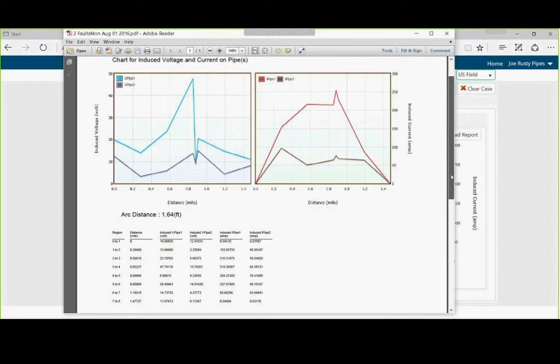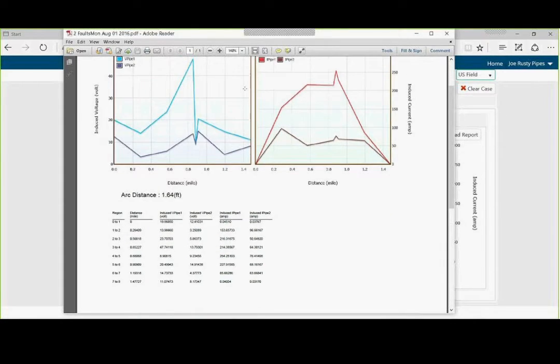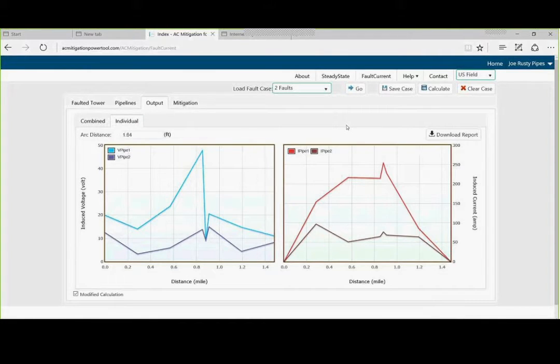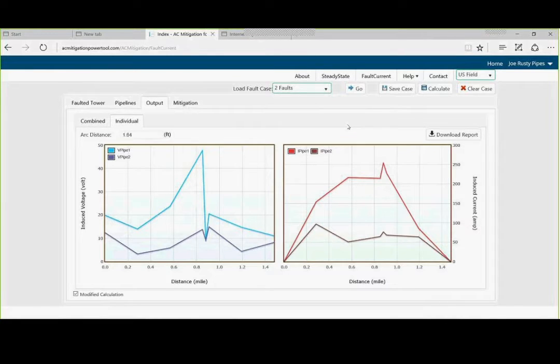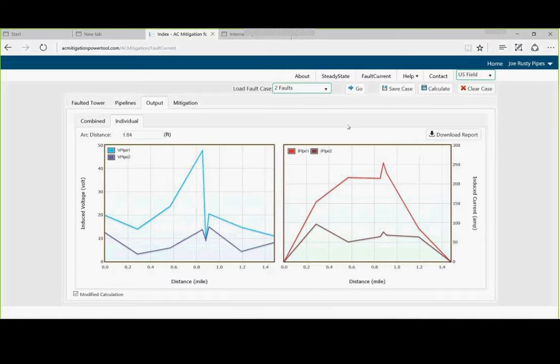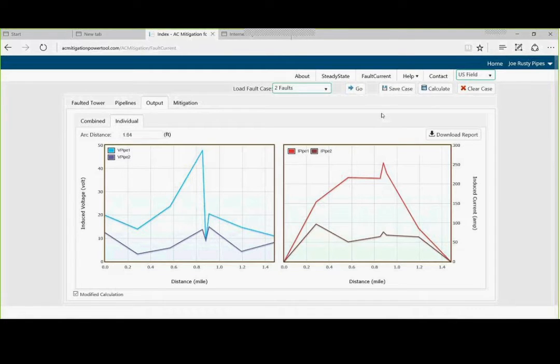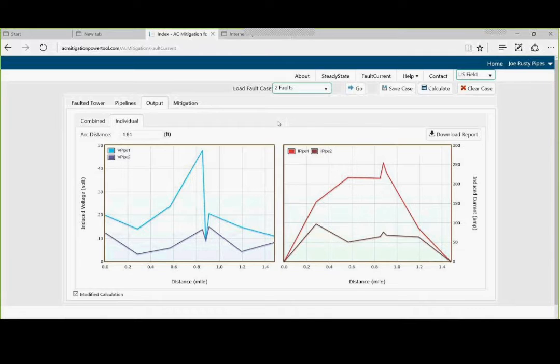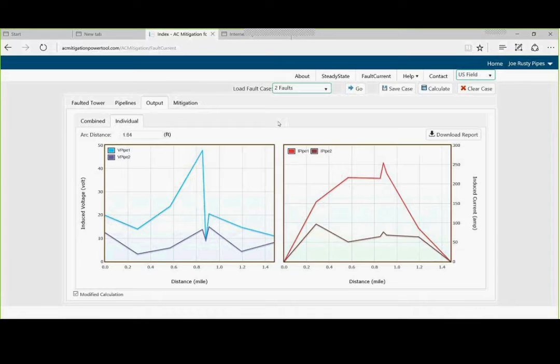The most important things you need to be aware of is when you're doing this. The most important thing is current. The current on the tower lines is important to know. The second most important thing to know is the coating conductance or coating resistance. I strongly urge that you do a good coating assessment of your pipeline using the coating conductance methods to determine that resistance. And your soil resistivities are a prime example of how AC corrosion can occur, particularly when you're less than a thousand ohm centimeter. It only takes volts, single volts sometimes, to cause AC corrosion. And this is one of the most important factors.